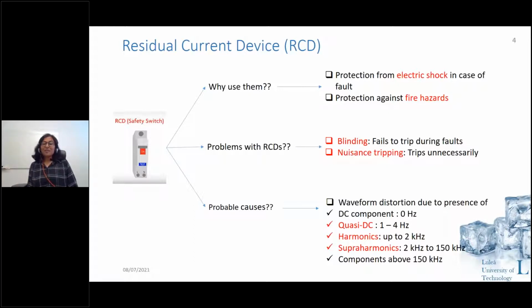But other than that, quasi-DC, which is like a low frequency AC between 1 to 4 hertz. The term quasi-DC, when we tried to search for it, we could find quasi-DC for the magnetic field of the Earth, which was around 4 hertz. So we mentioned quasi-DC between 1 to 4 hertz. Harmonics, of course, are very much known, up to 2 kilohertz. And then you have supraharmonics, which is 2 to 150 kilohertz, which we have seen in a lot of sessions in these 2 days. And then we have components above 150 kilohertz, which is conducted emission.